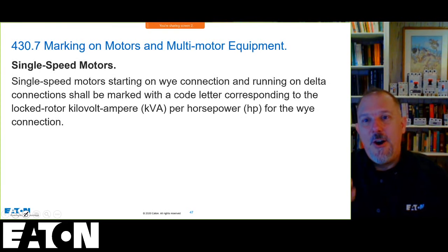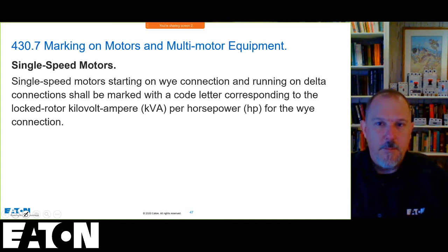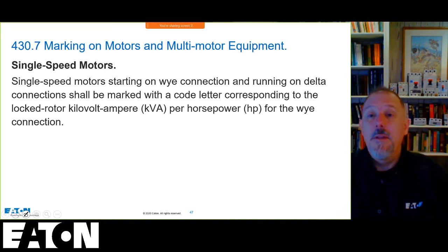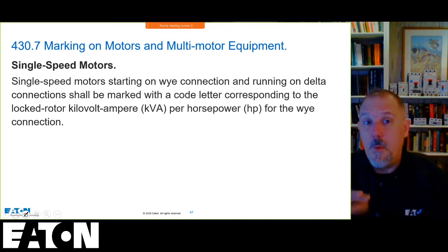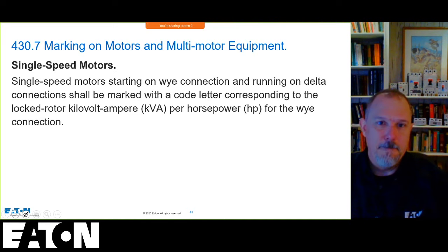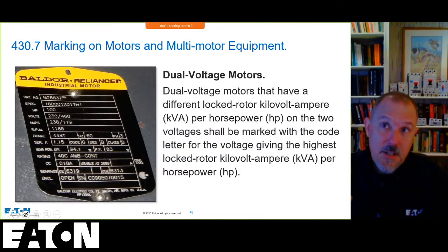Again, how we start these motors makes a difference as well. Y connected, some of these motors will be Y connected during start and then convert back over to a delta. And you've got to understand how they're started, because that will impact how you pick your overloads, how you pick other parts and pieces of that circuit. So it's important to understand whether it's a Y start or a across the line delta start, etc. And the nameplates, and the information you get from the manufacturer, will give you that info.